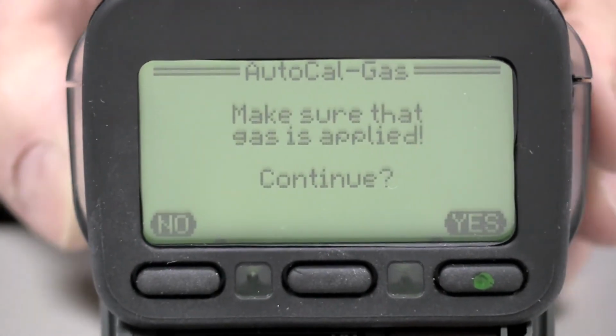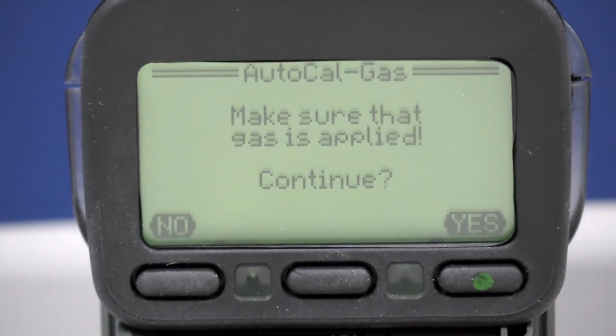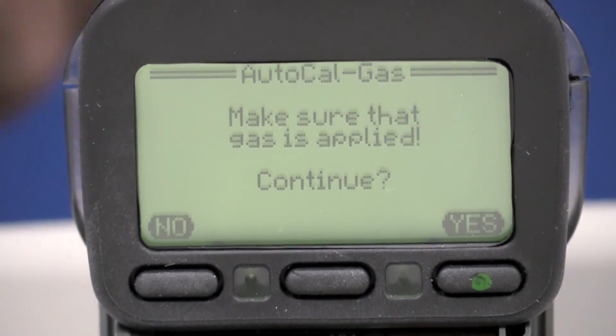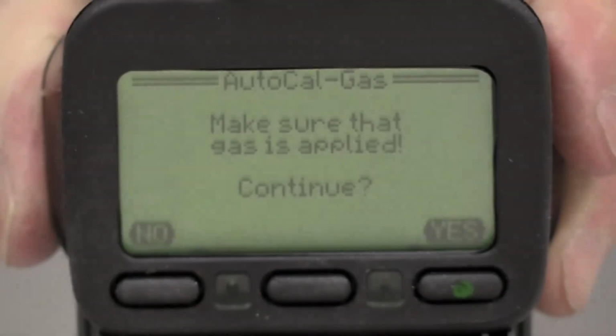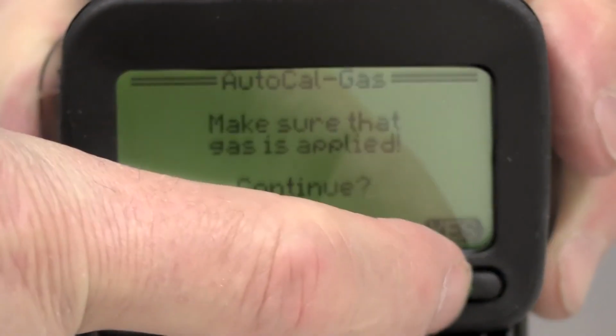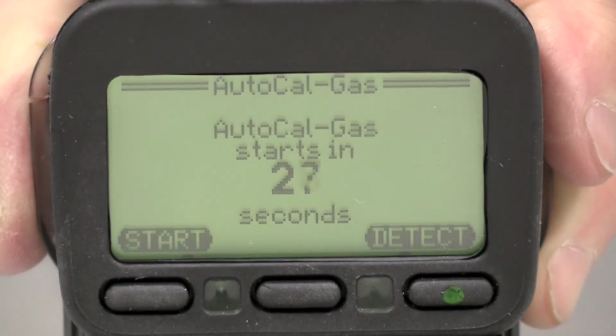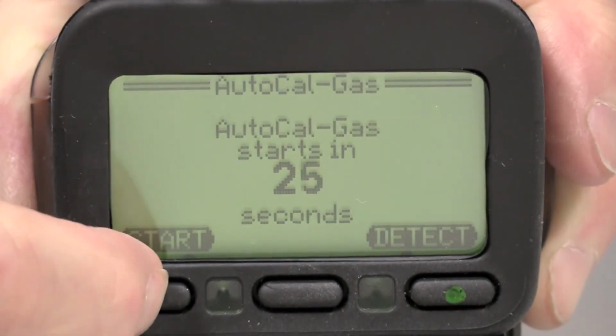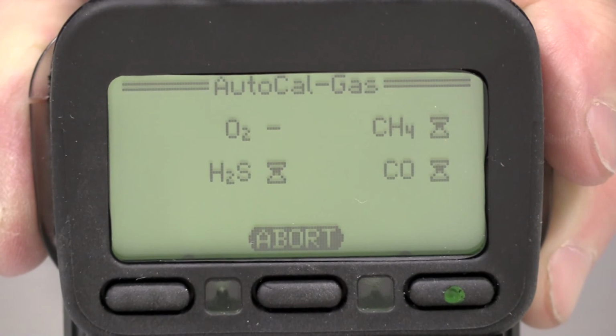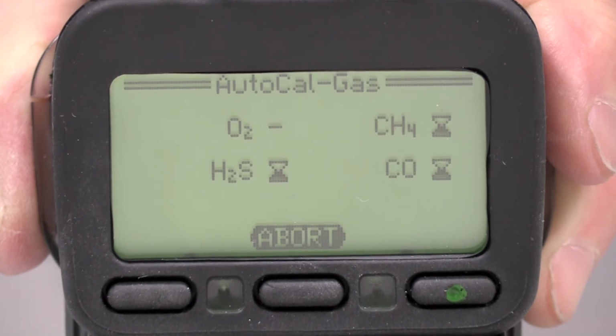The instrument will ask you to verify that the instrument is properly connected to the cylinder of gas. Press yes to continue. The instrument will count down the remaining seconds before beginning the adjustment. You can press start as soon as the gas flow has been turned on, or you can wait for the countdown to end and for the instrument to begin the adjustment procedure automatically. Pressing abort ends the autocal procedure without completing the adjustment.